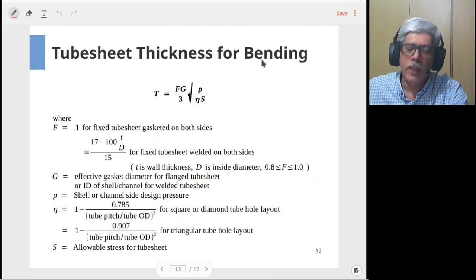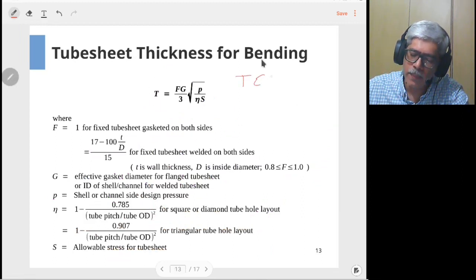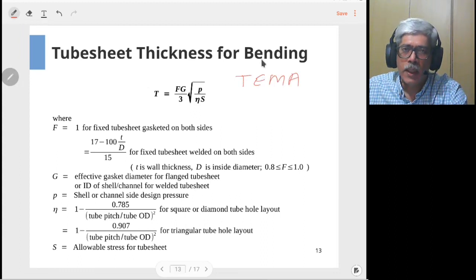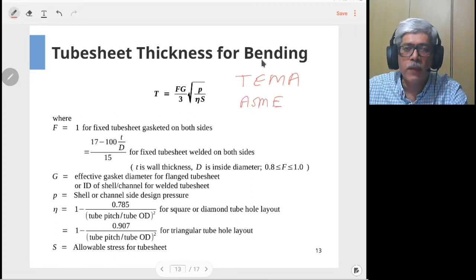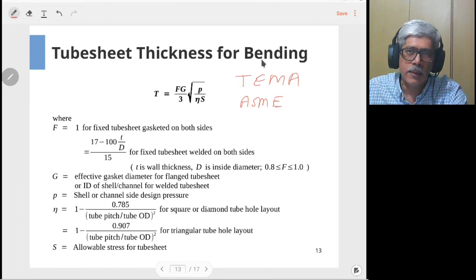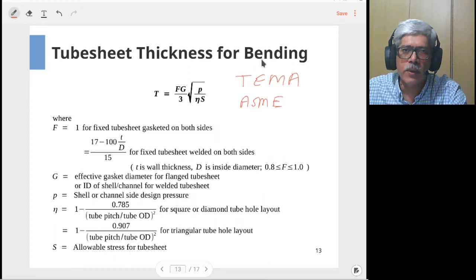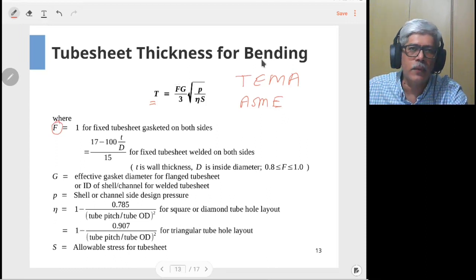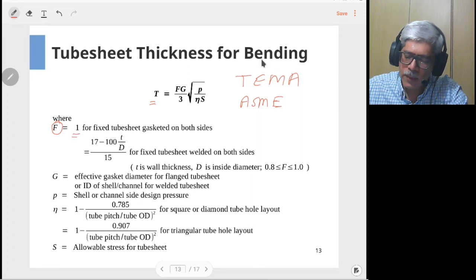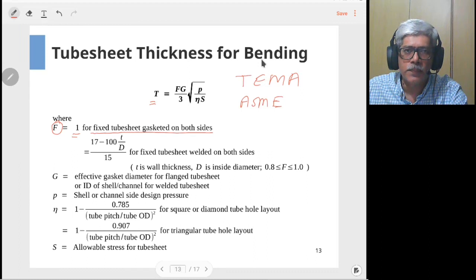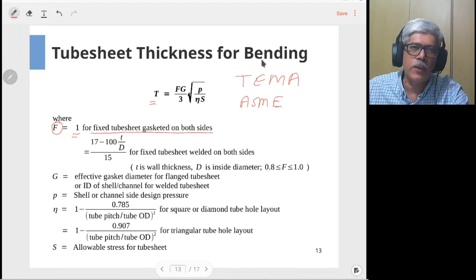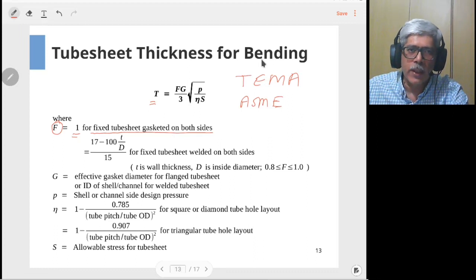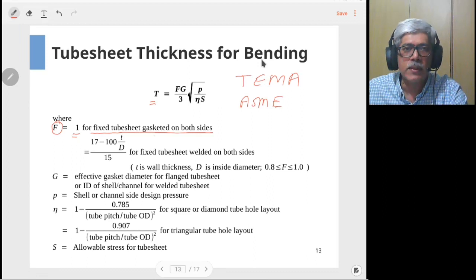First we'll look at the tube sheet formula against bending. These formulas are taken from TEMA, and ASME also has a modified version. The thickness of the tube sheet is given in terms of factor F, which depends on the type of tube sheet and how it is joined to the shell and tube sides. F equals 1 if it is a fixed tube sheet gasketed on both sides — that is, bolted joints on either side with gasketed connections.